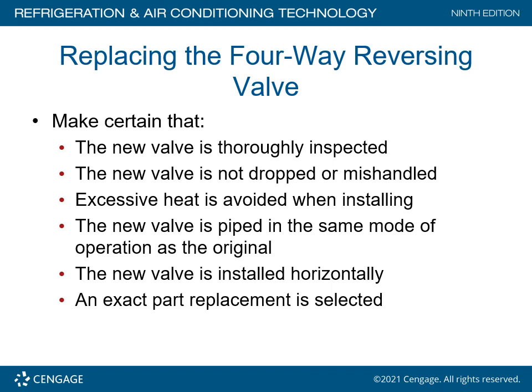Excessive heat is to be avoided when installing. It means you have to use the cooling rags, you have to use the heat paste, that kind of thing. The new valve is piped in the same mode of operation as the original. The new valve is always installed horizontally. You will never see a reversing valve installed vertically. If you can show me one anywhere out there, I would like a picture of that.